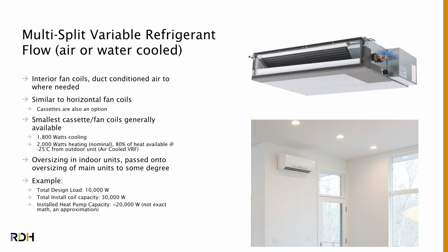And then now moving into VRF. So now we have refrigerant lines throughout the building. We're doing all our heating with heat pumps. Could be a water-cooled heat pump connected to a geo-exchange system. Could be a water-cooled heat pump connected to a boiler and a cooling tower. Could be an air-cooled heat pump, air source heat pump. The big limitation here is how small can you buy the cassettes, whether it's a wall-mounted cassette or a vertical fan coil or a horizontal fan coil in the ceiling.